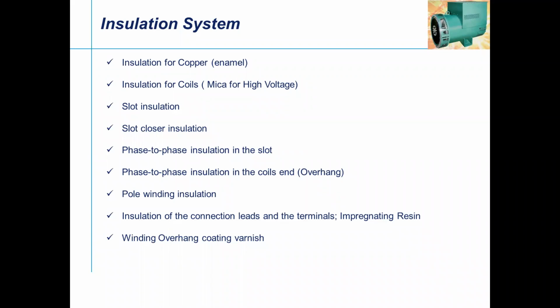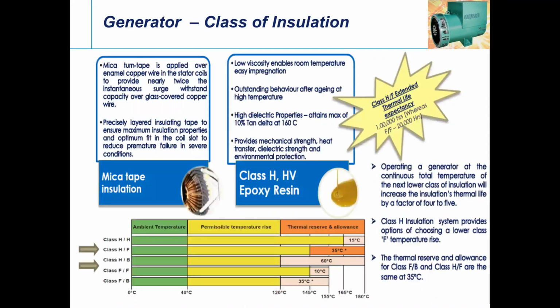So insulation of the connection leads on termination: after the complete winding, it goes for the vacuum impregnation process, which is VPI, a very, very critical process in generator manufacturing. And for the winding overhang, for coastal applications or moisture environmental reasons, there is one more coating of varnish done on the winding to protect it from that environmental condition. So coming to the generator insulation on the mica tape, there is the class of insulation, class H insulation.